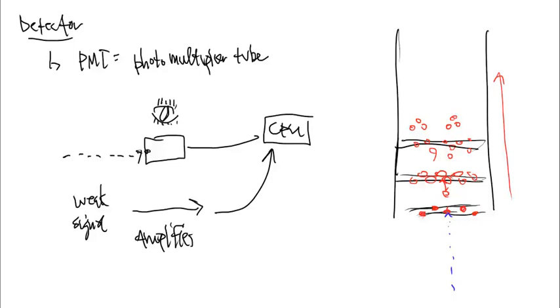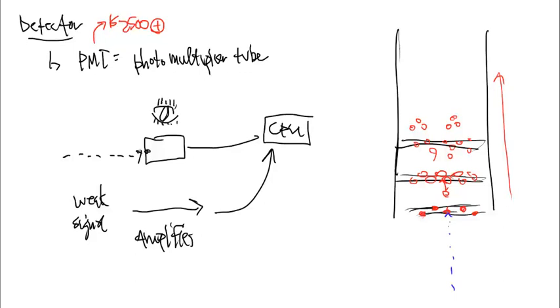You might be surprised to know that these detectors can cost thousands of dollars. This little photomultiplier tube, these things can run $2,500 or more, and just like with a light bulb in a way, these things can go out. They can stop working, and they need to be replaced. And sometimes the machine is so old that the cost of a photomultiplier tube, basically, you might as well buy a new instrument. You'll get a better instrument, you'll get an updated version of the instrument, and you'll get a working instrument at the same time versus paying $2,500 or more just for a PMT that needs to go into the instrument itself.